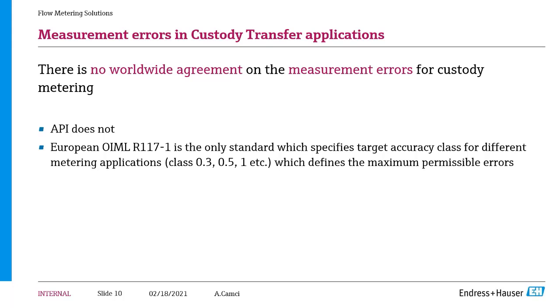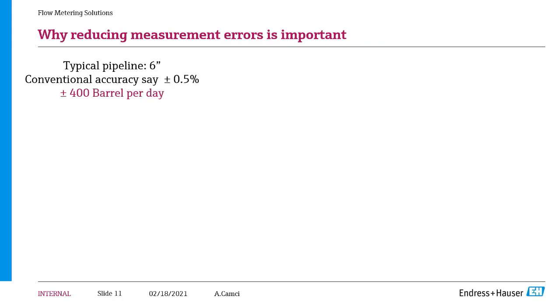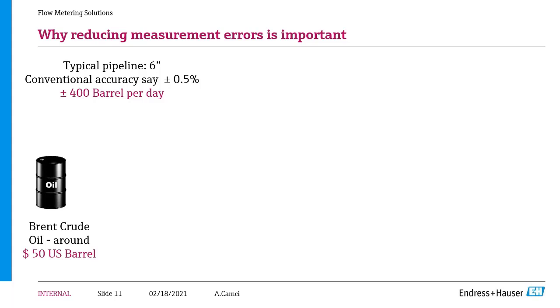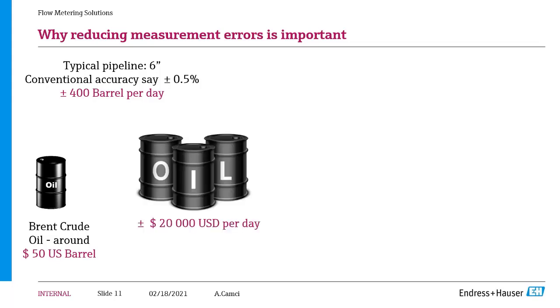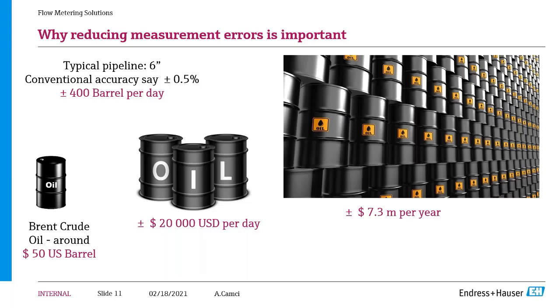Here, why reducing measurement error is important, I will give you a real life calculation. A typical pipeline of 6-inch, if you measure with a conventional accuracy, say 0.5%, you are not sure about 400 barrels per day of the measurement, whether you are buying more or less, or paying more or less. If you consider 1 barrel of oil is $50 per barrel, at around today's price, then you are unsure about $20,000 per day if your payment is correct. If you see it over a year, it is almost higher than $7 million per year.